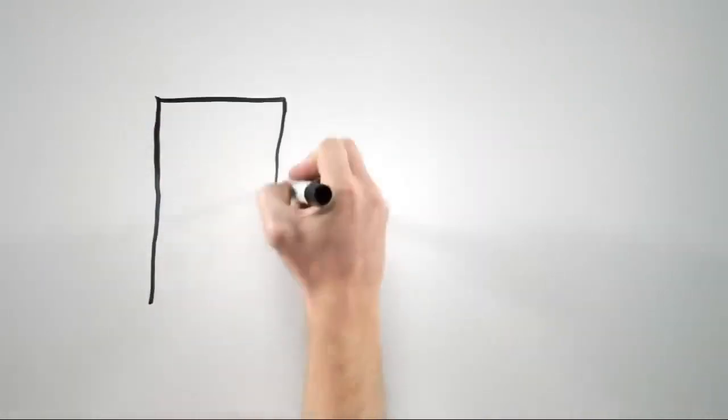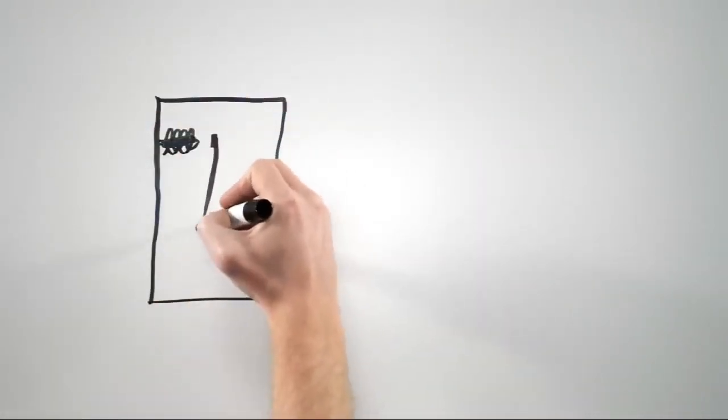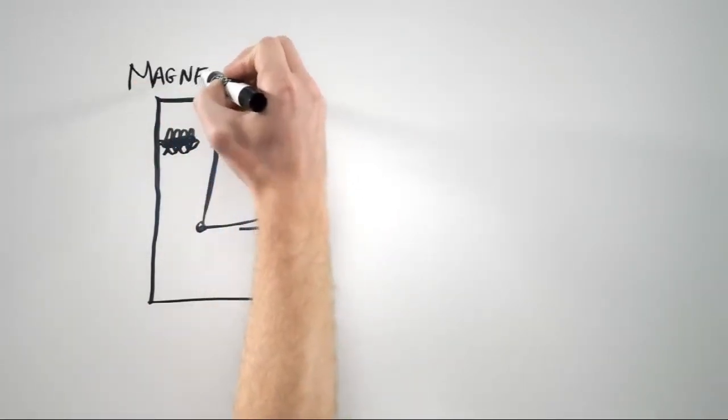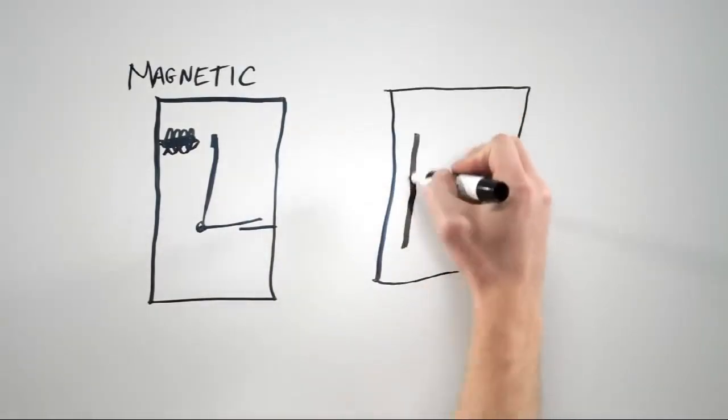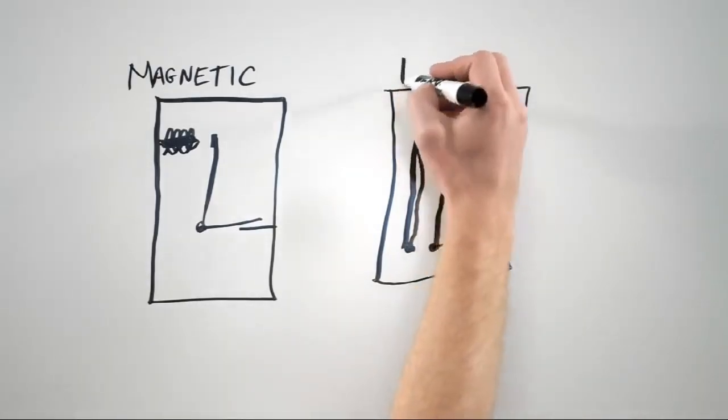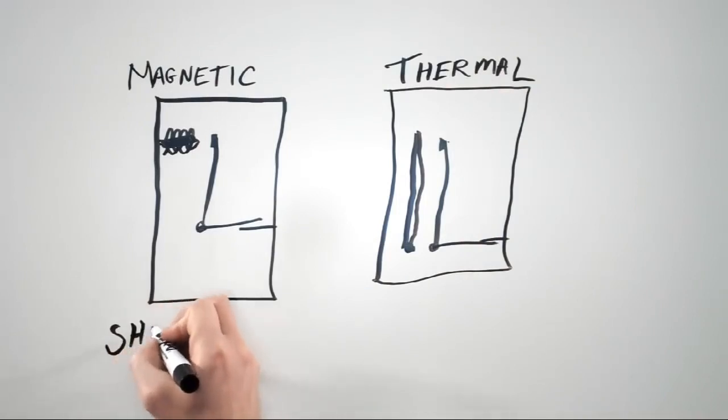Going back to the circuit breaker, we've got magnetic protection built in and thermal protection built in. Magnetic protection reacts to a very high level of current very quickly, so it is suited to protect against short circuits. Thermal protection is a slower reacting protection and correlates to the amp rating you see on the front of the circuit breaker. This is to prevent against over current.